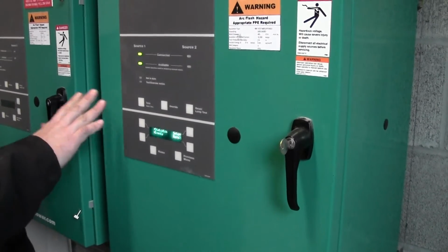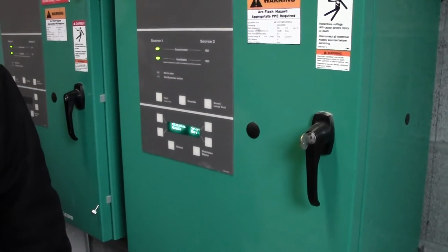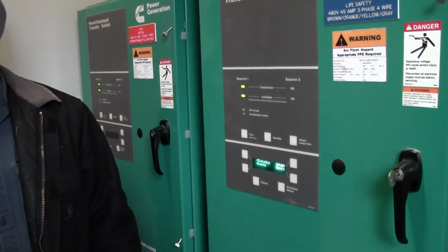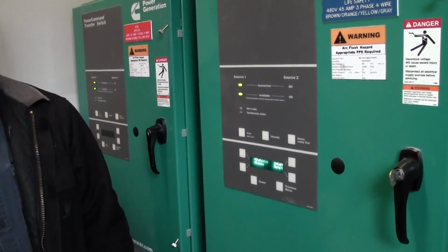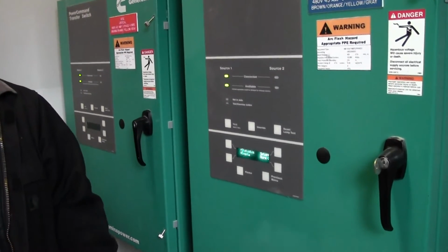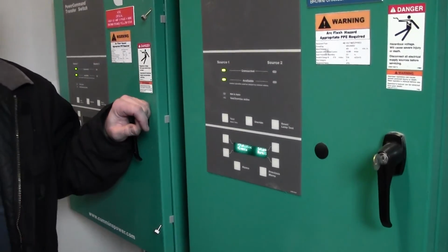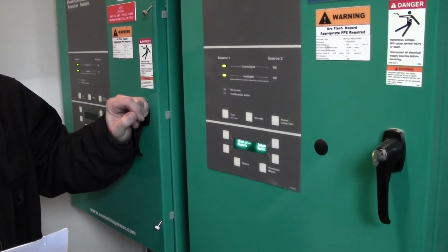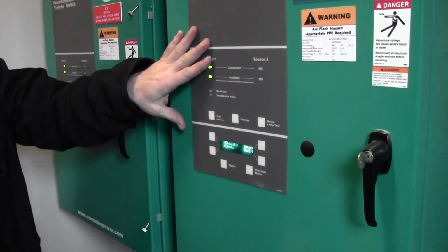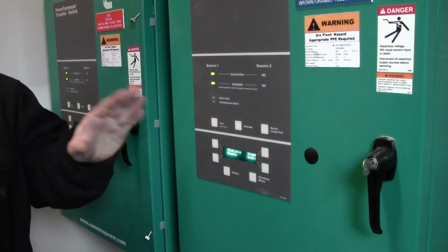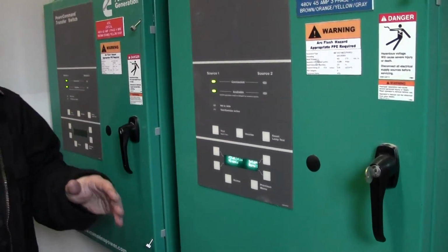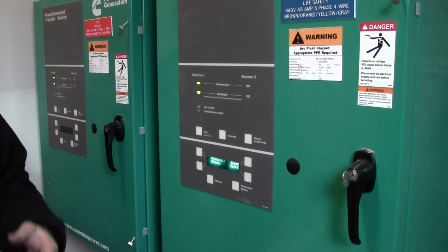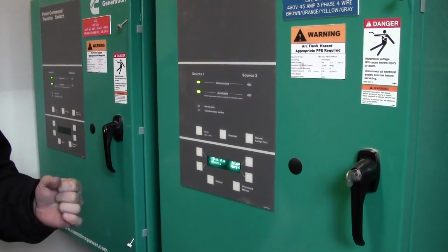But let's say we put all of these into test with no load. You can go around, push all the buttons in it. All it'll do is start the gen, and we'll transfer it over to the generator and let it run. You have to do that, transfer it, depending on what category you are. Right. But if he just wants to do a test from here, just start it, run it, make sure the switches are all working, because that tells you that my remote start wires are working fine, they all three start the generator. You just want to transfer it. Right.